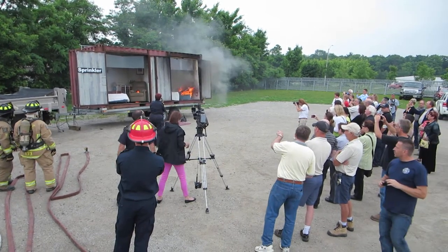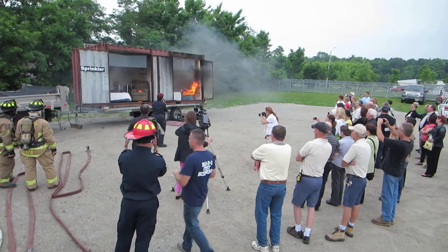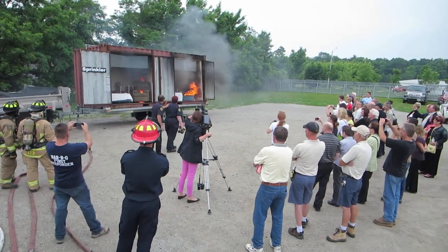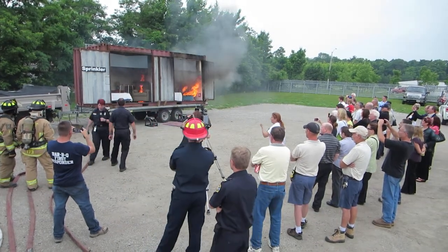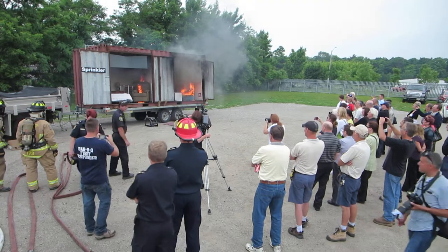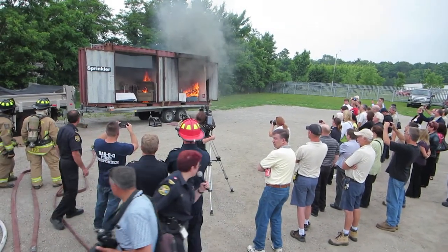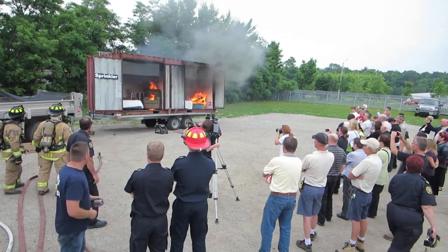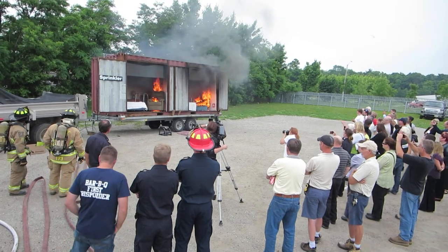The fire itself is 370 degrees Fahrenheit. The room is at 114 Fahrenheit at the top of the smoke. We're not quite a minute in yet, and that's what your rooms are looking like.